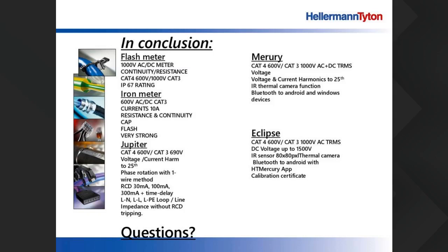And our last meter, of course, is the Eclipse. It's also a clamp meter for 600 volt TRMS. It measures DC voltage up to 1500 volts, which is a unique feature on this meter from the supplier. Then it's got the thermal camera. It's got an 80 by 80 thermal camera. It's got built-in Bluetooth that can connect to your Android phones. It uses an app called HTMercury, and it also comes with a full calibration certificate.